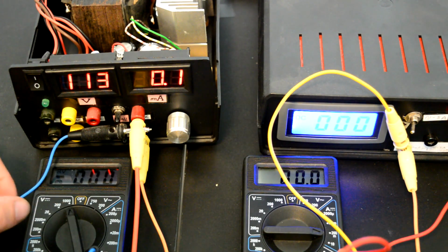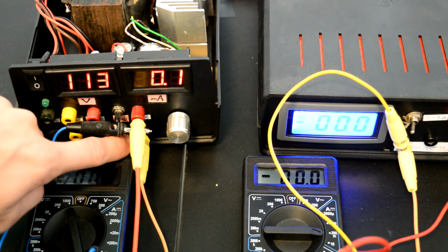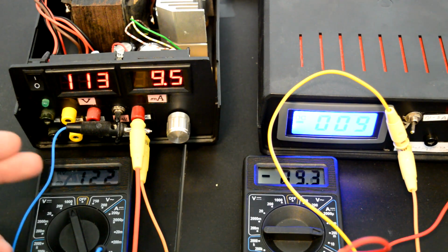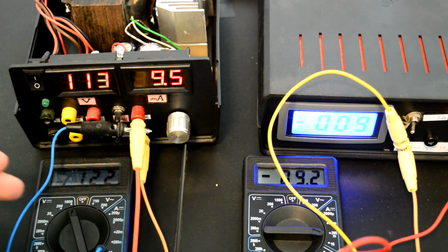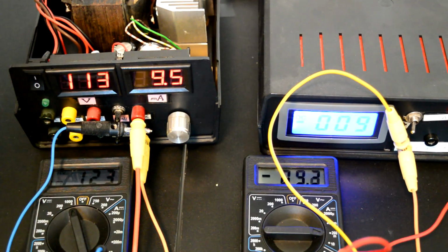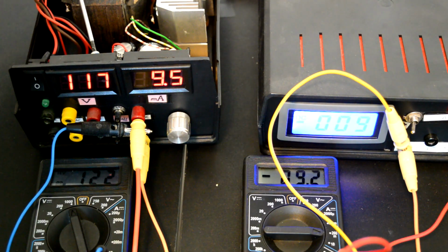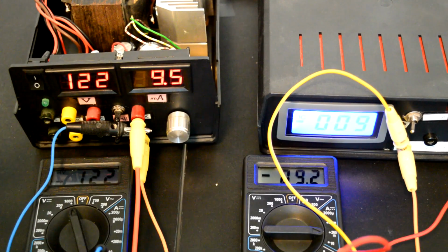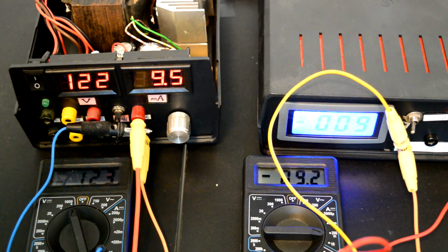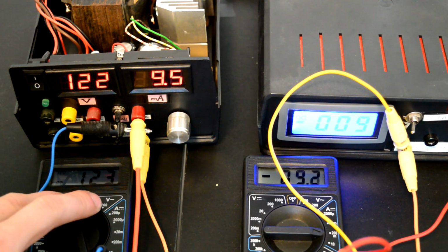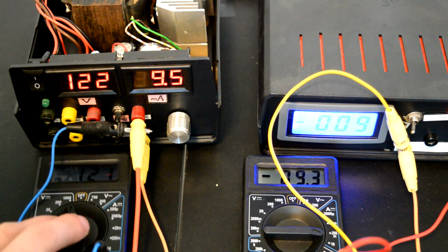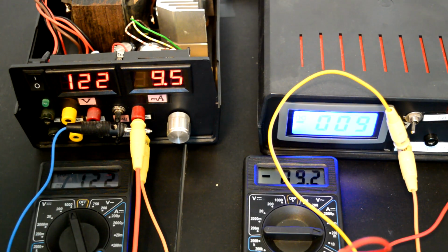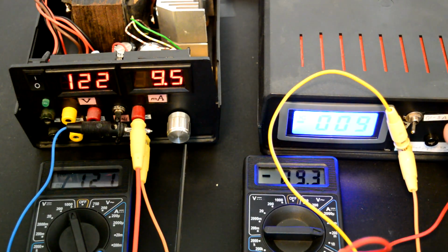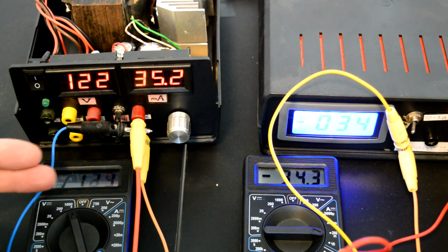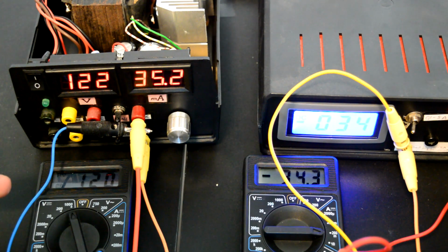So if I turn on my output, without shocking myself of course, we can see that there's a small error in the voltmeter, but this can be fixed by calibration. Fortunately, I have a screwdriver lying around. There we go. Periodic calibrations of your equipment is essential. And now we see that we have 122 volts set. And my multimeter is somewhat good. And now if I change the load, so I go from 9 milliamps up to 20, 30 something, we see that the voltage is maintained. So there's no large variation in the output voltage.